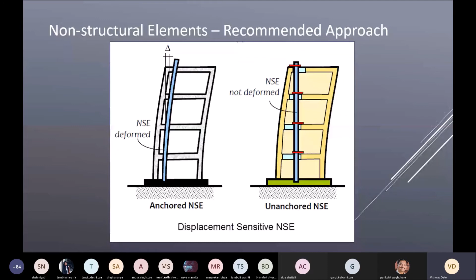So if this pipe is supported but is allowed to remain vertical despite the movement, right? You basically create holes in the floor of certain size, so that even if the building goes to the left or to the right, the pipe still remains vertical. You see the understanding in this: the pipe should not move with the building. The pipe should remain vertical during the earthquake, which still should get supported, but should not move. So a simple thing like this will spare the damage that it would have caused.